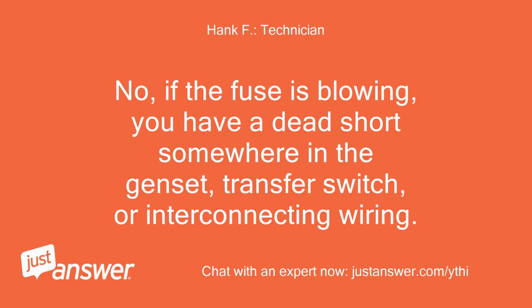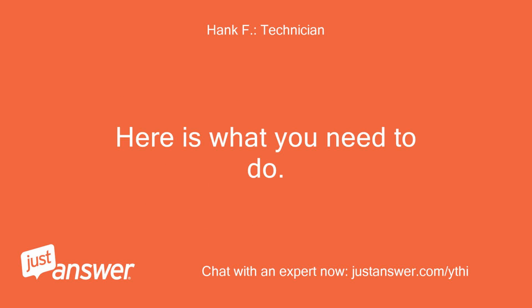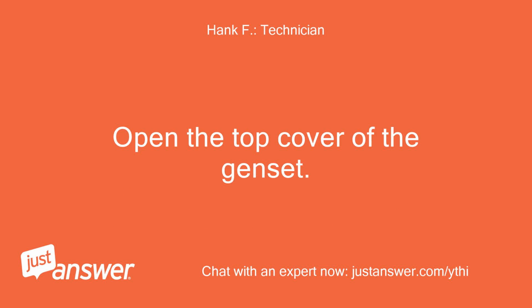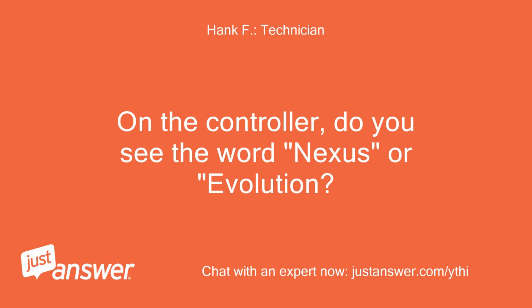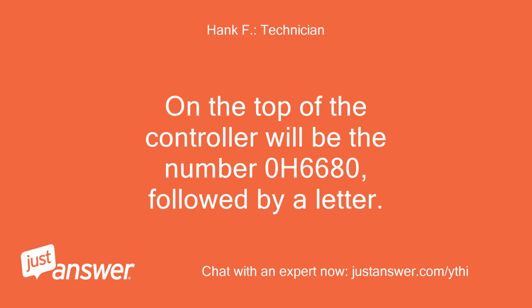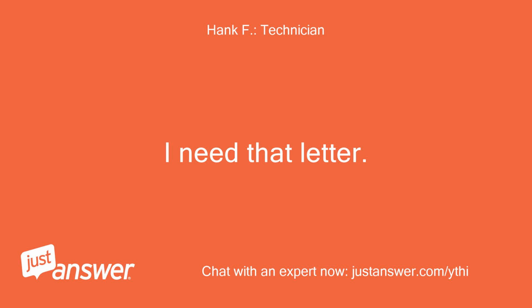No, if the fuse is blowing, you have a dead short somewhere in the genset, transfer switch, or interconnecting wiring. Here is what you need to do. Open the top cover of the genset. On the controller, do you see the word Nexus or Evolution? On the top of the controller will be the number 0H6680, followed by a letter. I need that letter.